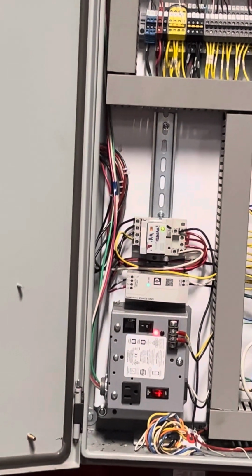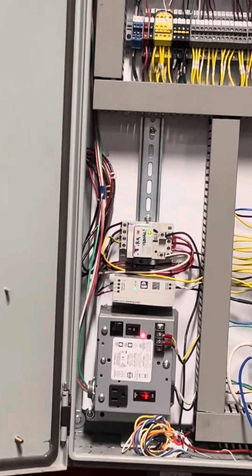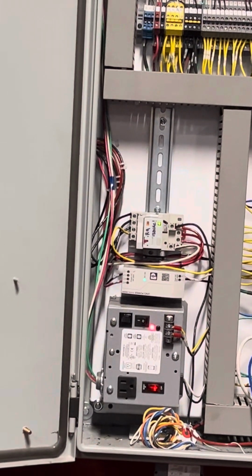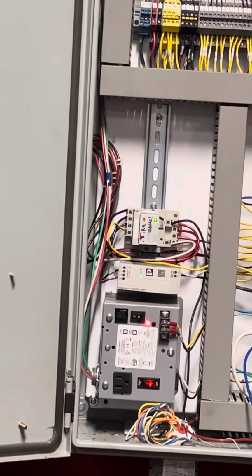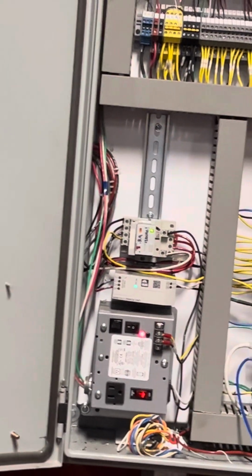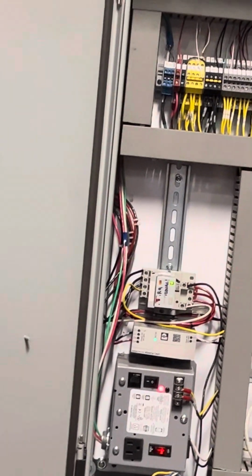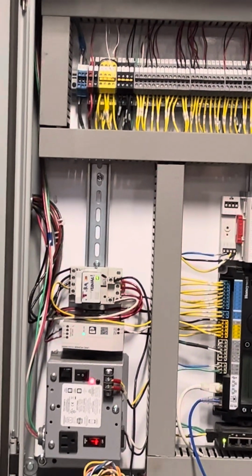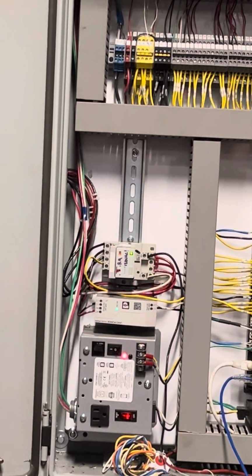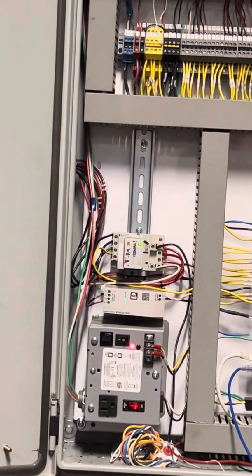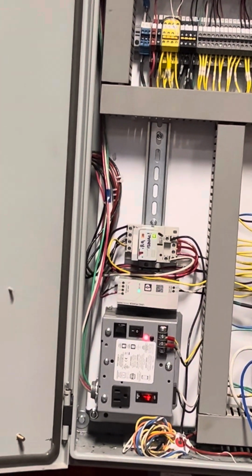Similarly, if you wanted to prevent these, just removing that relay would do the same thing. It's just going to shut down the BMS system because the BMS is not getting a signal. It's going to shut down the three boilers because they're no longer getting a closed contact for the CO and glass break shutdown. That makes sense?